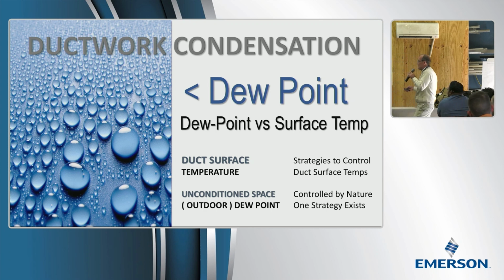This is for all those times that, for whatever reason, you have no choice. You have to put the ducts in a vented attic, a cool wet parking garage, a crawl space, wherever it happens. Since this is all about dew point versus surface temperature, and we can't control the dew point, this is all going to be strategies for how you can limit how cool the surface temperature gets.